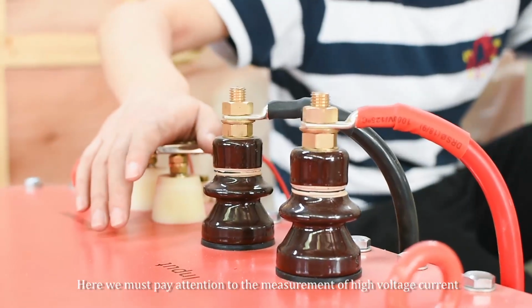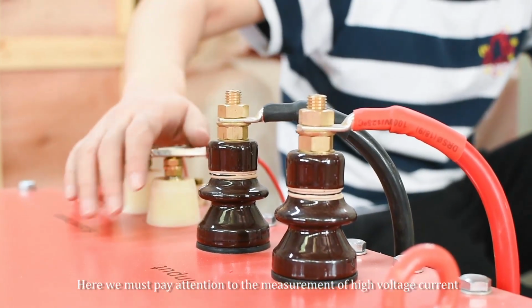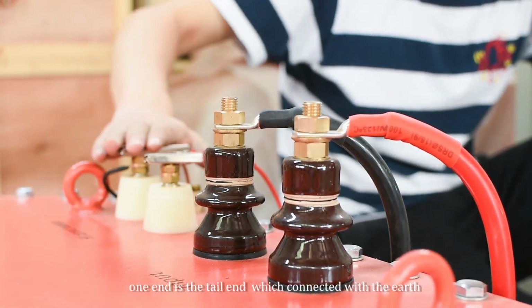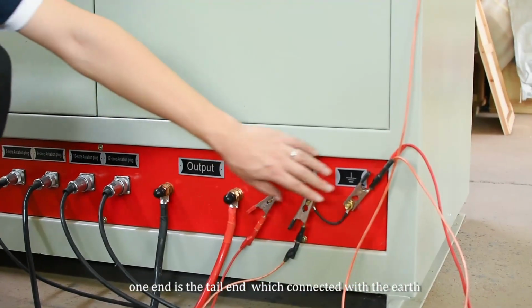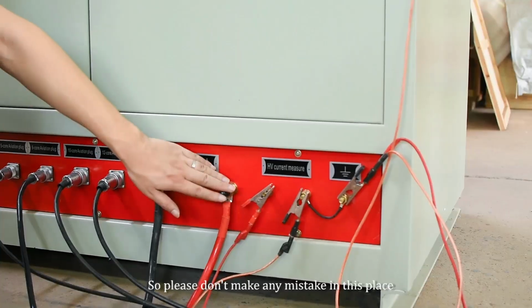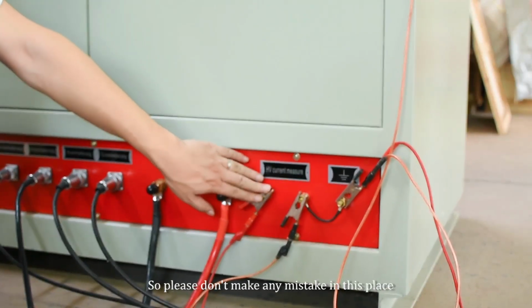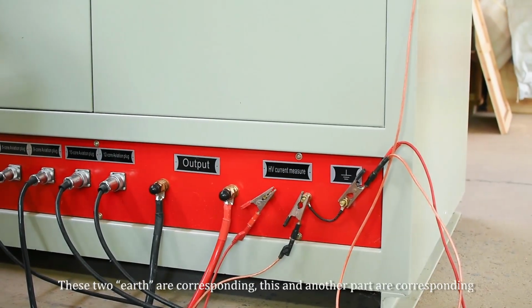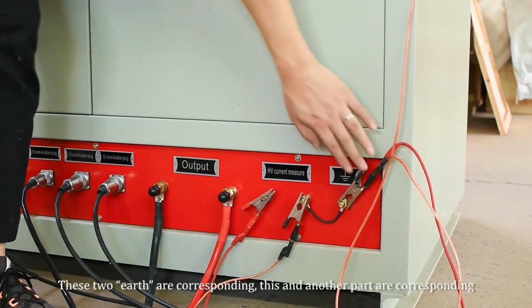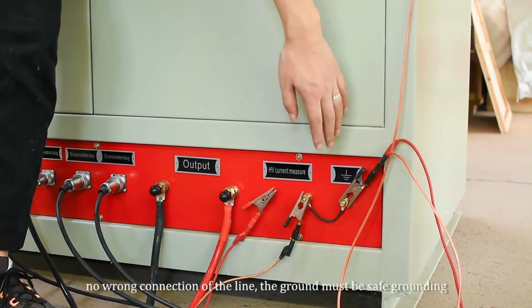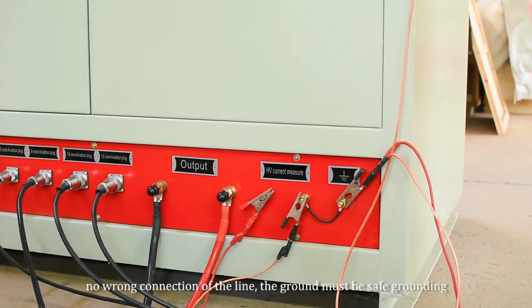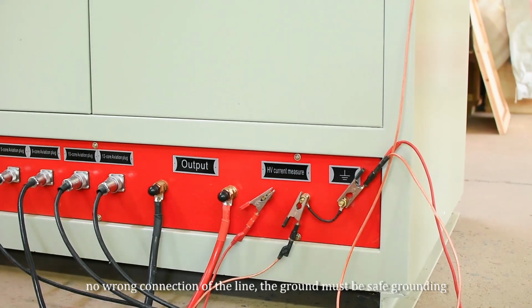Here we must pay attention to the measurement of high voltage current. One end is the tail end, which is connected with the earth. So please don't make any mistake in this place. These two earths are corresponding. This and another part are corresponding. No wrong connection of the line. The ground must be safe grounding.